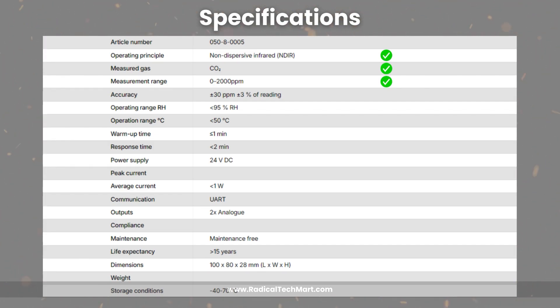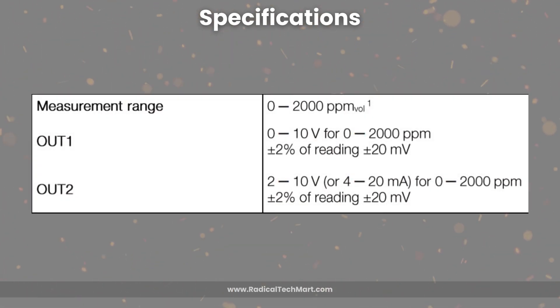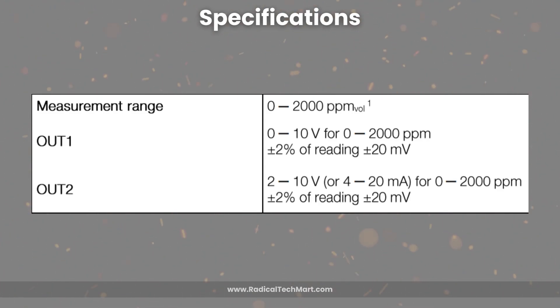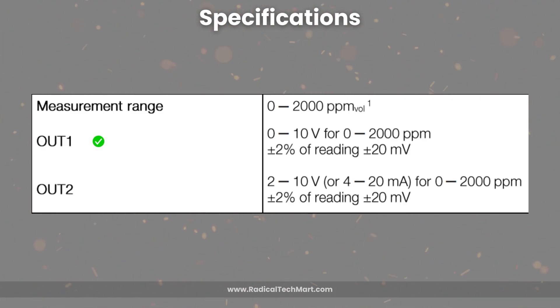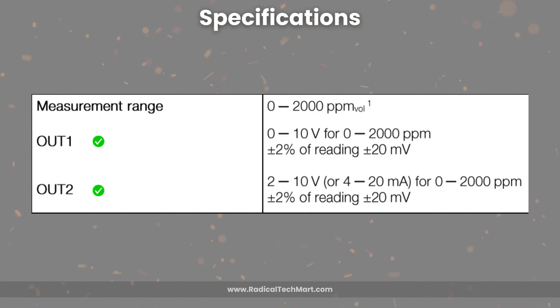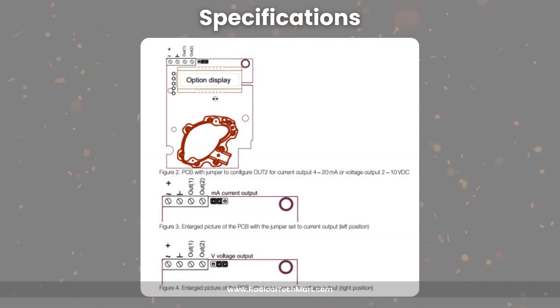Note that it is also available in different ranges up to 10,000 ppm. This CO2 transmitter has a dual output setup. Output 1 transmits data in voltage ranging from 0 to 10 volts for 0 to 2000 ppm respectively. Output 2 has the option of both 0 to 10 volts and 4 to 20 mA. You can select either option by adjusting the jumper available on the sensor circuit, whose location can be seen on screen right now.